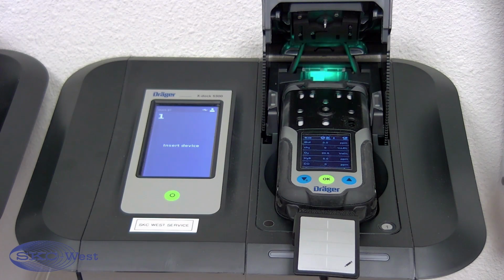We are now going to be going over the X-Dock bumping and calibration station. Using the X-Dock is the easiest and preferred method to bump test and calibrate the X-am 3500 and 8000 series. Reminder, to expedite the process, please turn on all of your instruments approximately 5 minutes before you plan to bump test to let them warm up. Typically, the X-Dock is set up to bump test every day and the calibration frequency is determined by the sensor. This will allow the X-Dock to do the bump test every day, and if calibration is needed, either by frequency or if a bump test fails, it'll automatically calibrate.